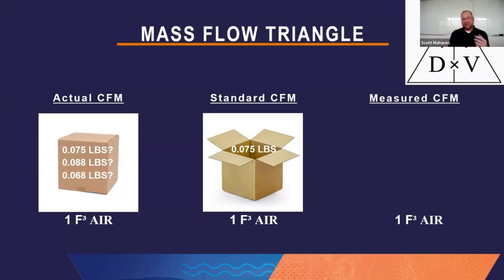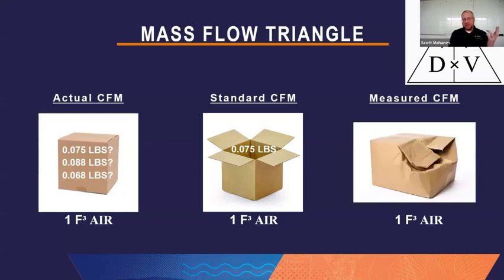Measured CFM, this is kind of funny, comes in a little bit damaged. We don't really know what we have here when we have an uncorrected value that's just the displayed measurement being done. That's not always the case. Sometimes you are close enough or right at standard density conditions, or you don't need to worry about changing for temperature.